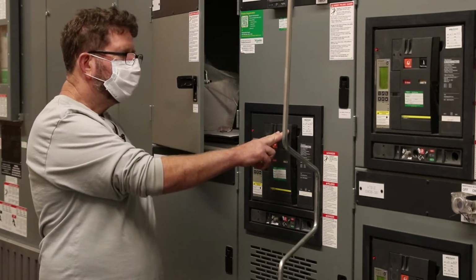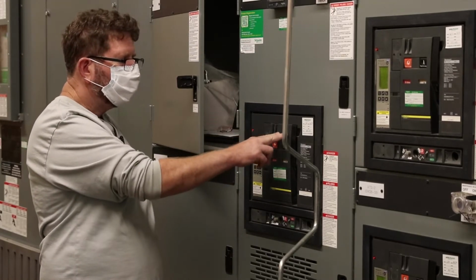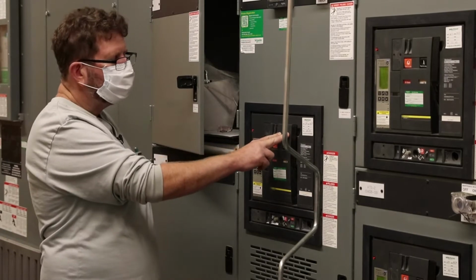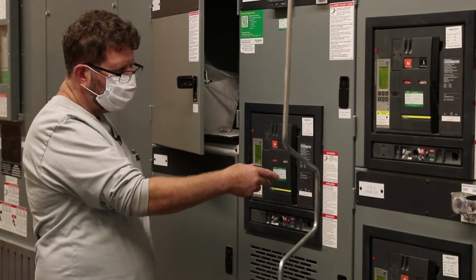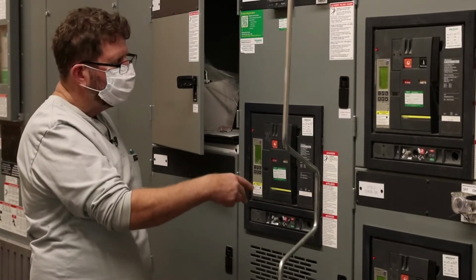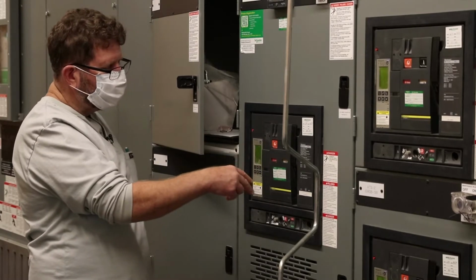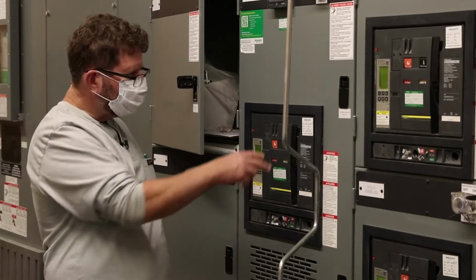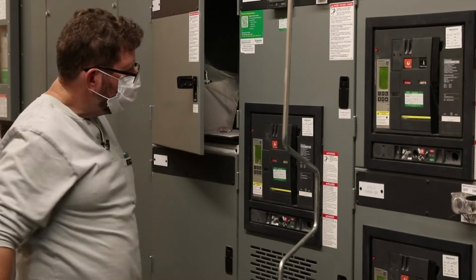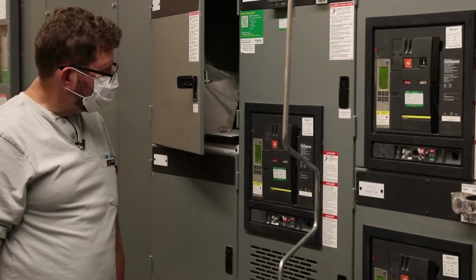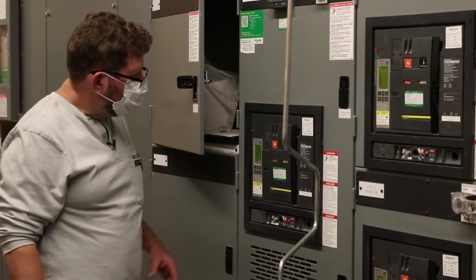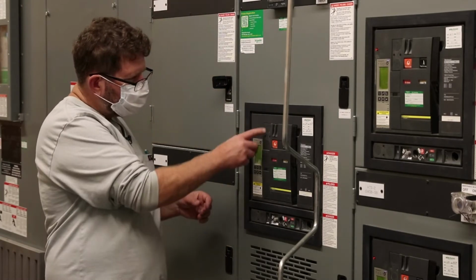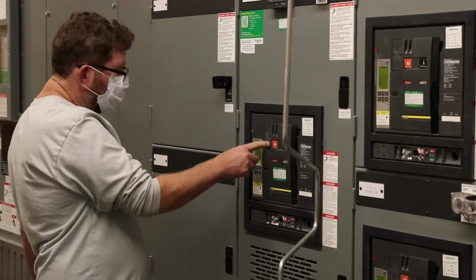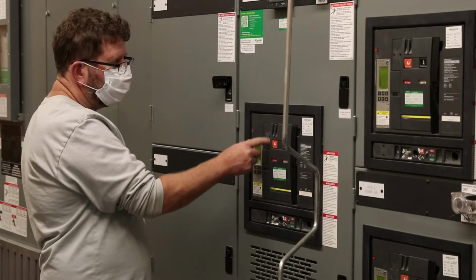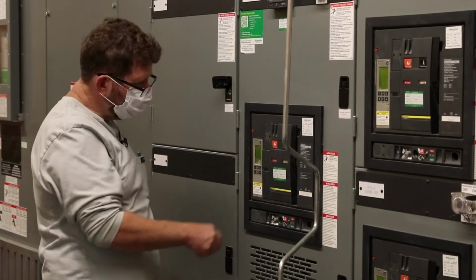You can have a shunt trip which trips the breaker through controls. If that's in and energized, it would say charge not okay. Or if you have an under voltage coil that's not satisfied, it would say charge not okay. Again, this is a padlock attachment. The Kirk key that should match the HVL should go here.